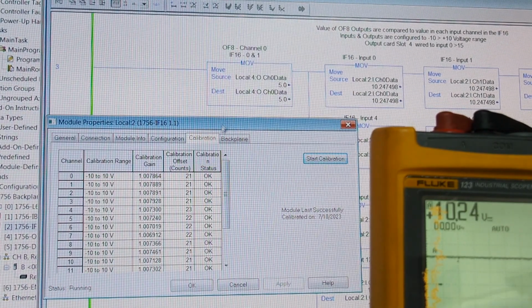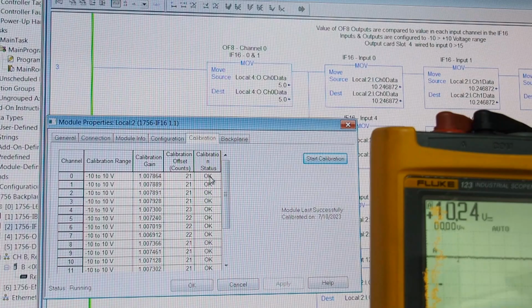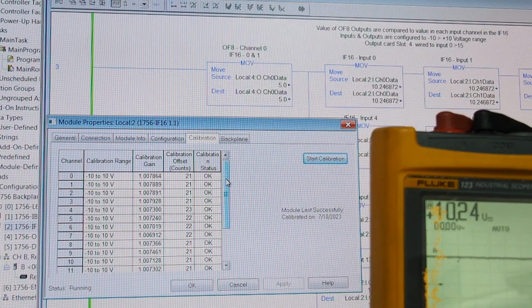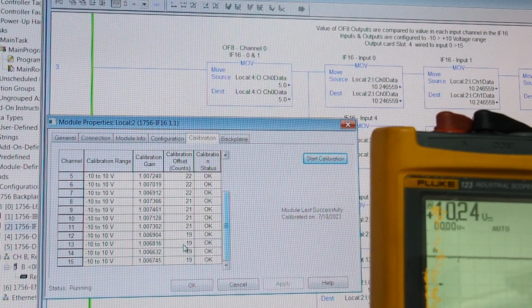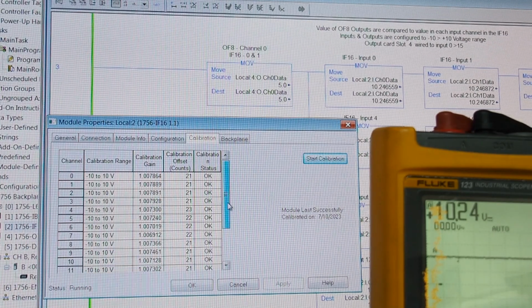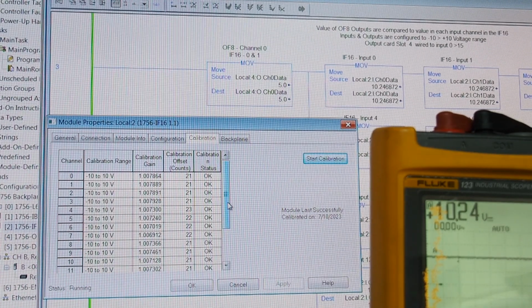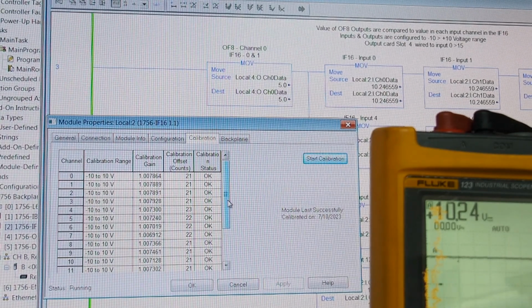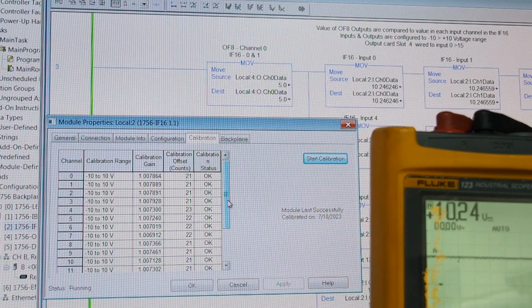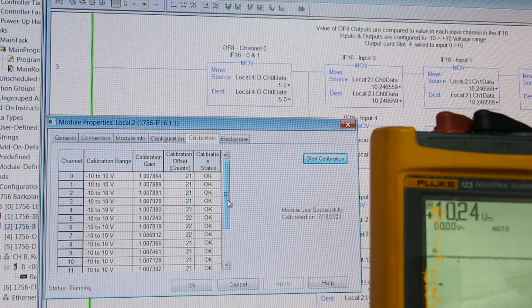And we have a look here. Always check this calibration tab in your module properties to make sure that everything is good. Because you could have a bad channel down here in the bottom if you haven't scrolled down, and it'll be out of calibration. Depending on what your system is doing, you could run into all kinds of problems.